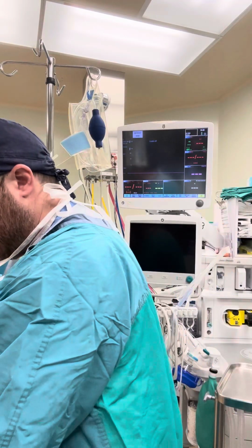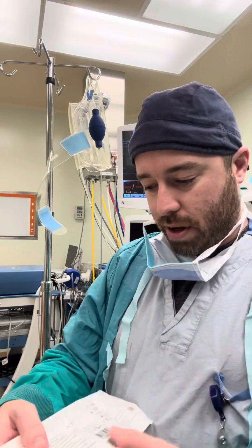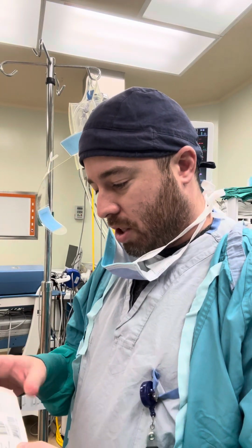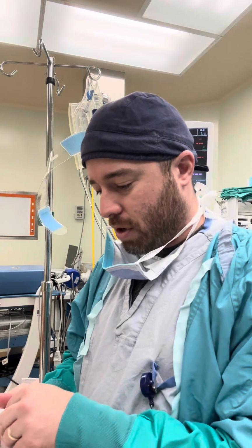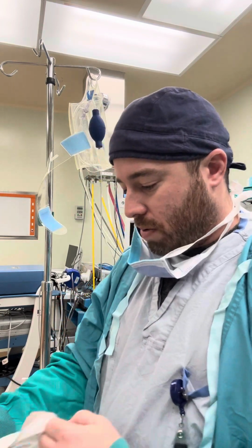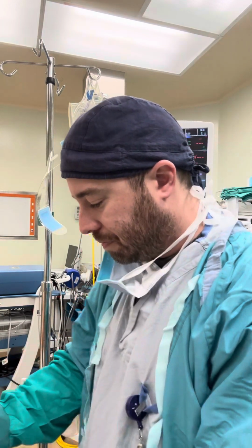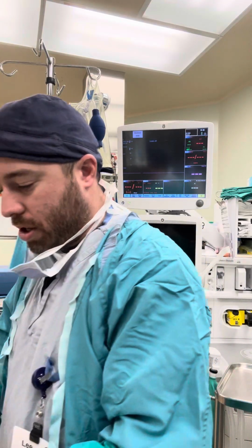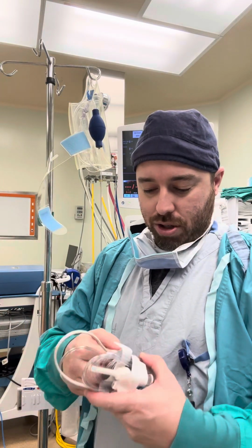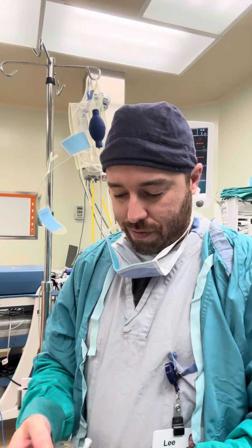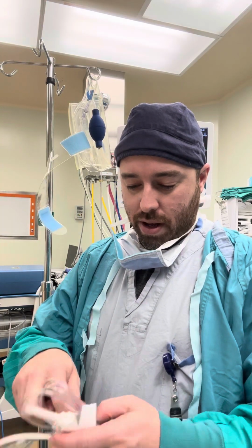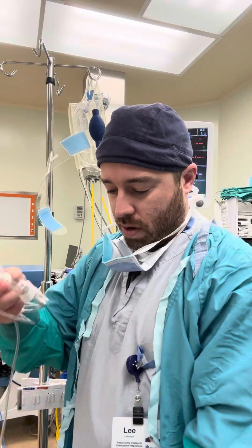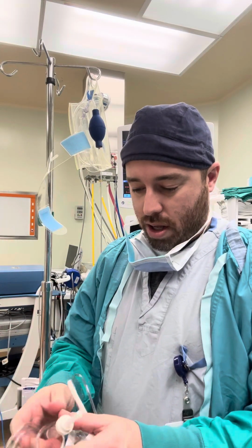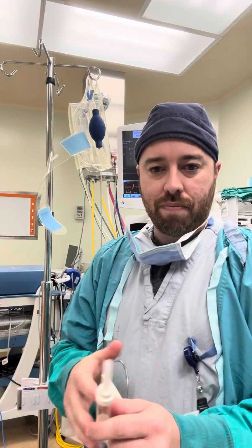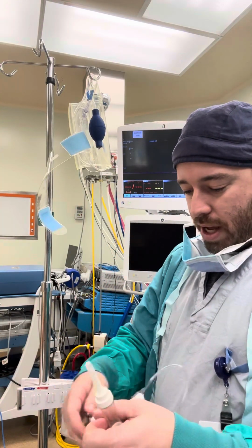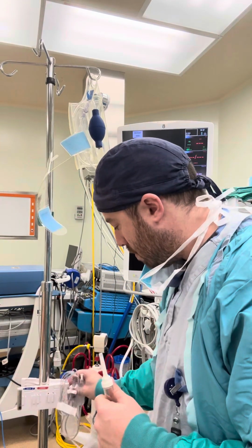So I set this onto the bed here. We open our TruWave, and again, checking our expiration dates, 2026, May 21st, so that's fine to use. We open our package, and first I withdraw the transducer. When I withdraw the transducer, what I generally do is I just remove the first outer layer of the wrapping, and then I have my system here. What I do then is I place it into the transducer holder so I have a spot to hold it.